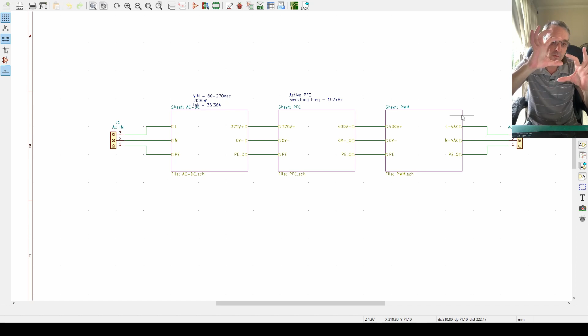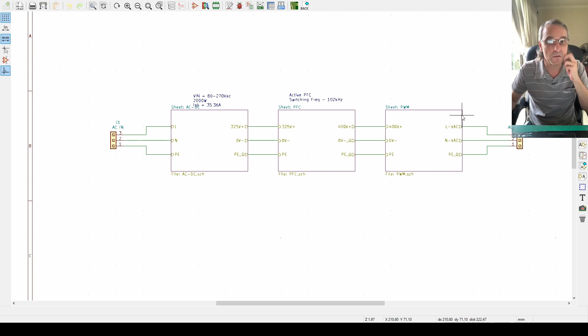Why is that important? Well, think of it like this, without going into too much detail. If you had a beer, and in the beer glass you had some beer, and on the top you had the foam, in South Africa you're paying for the whole glass, so the beer and the foam. So you want more beer, in other words, more power that you can actually use, and less foam. And that's what we're trying to do with power factor correction.